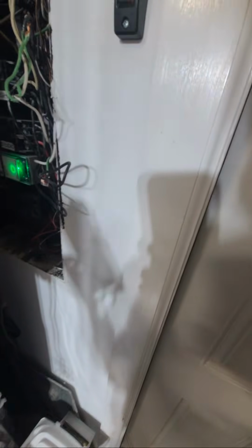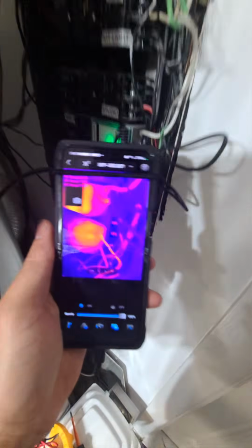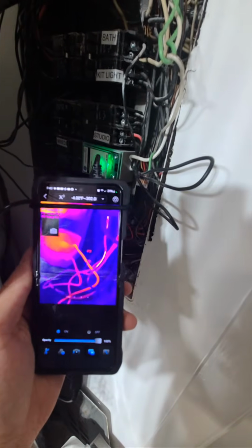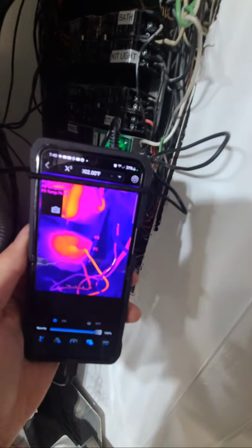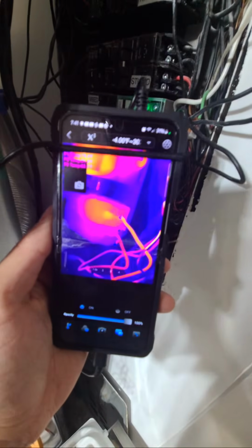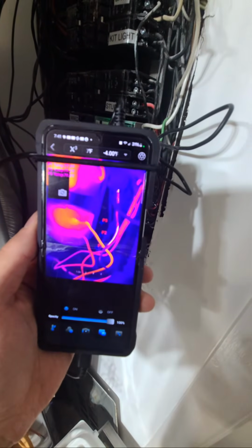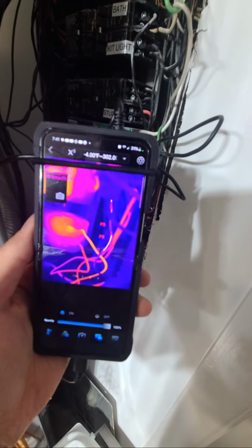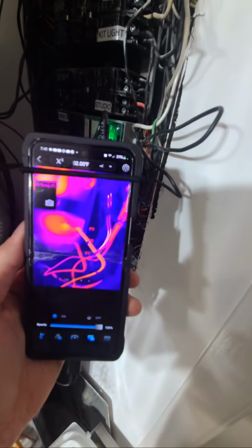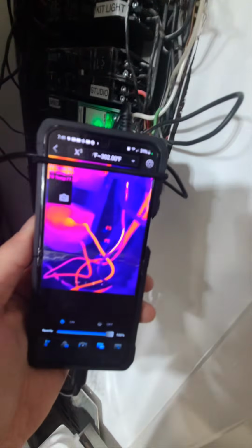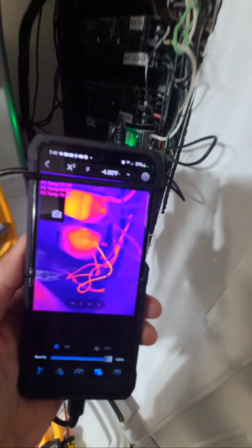As soon as you get to your panel, when you turn this on and you think you might have a loose connection, you can take your infrared camera immediately and just say, yep, definitely looks like a problem here. And if that wire doesn't change color pretty soon, we might have broke that breaker. But that's okay, because we're showing you guys on the stream basically the possibilities of failures. We created a failure purposely, and usually when you have a failure like this, it does break the breaker and ruins the connection. So we'll just have to see how that's going to act.